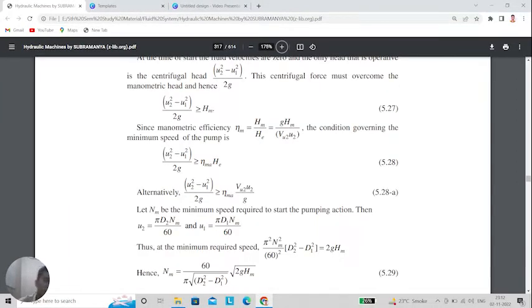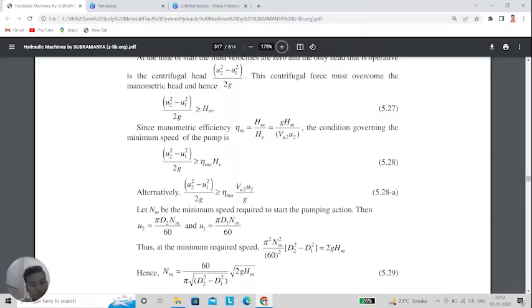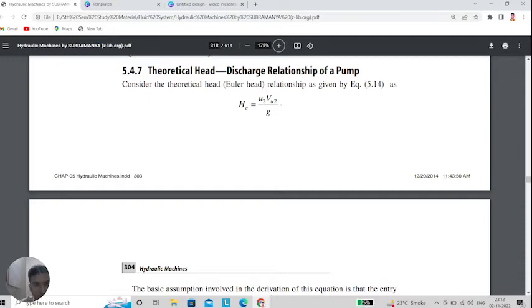The minimum speed required for running any pump is given by: N = 60 / (π × √(D2² − D1²)) × √(2g·Hm), where D2 and D1 are the two different diameters of the impeller and Hm is the manometric head. An important concept is the theoretical head-discharge relationship. Since Q equals A×V is constant throughout the channel, considering the theoretical Euler head and the relationship from equation 5.14, the Euler head is U2·Vu2 / g as derived from the velocity triangle.